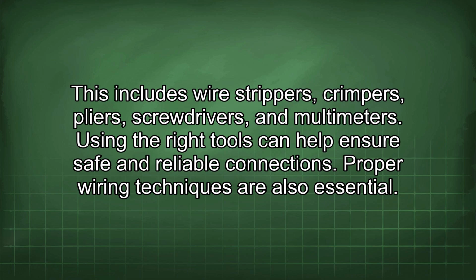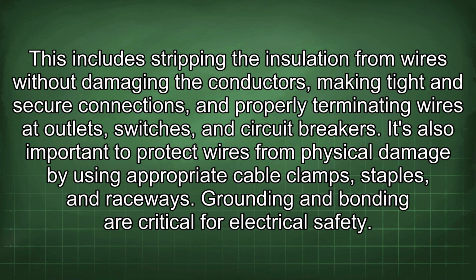Proper wiring techniques are also essential. This includes stripping the insulation from wires without damaging the conductors, making tight and secure connections, and properly terminating wires at outlets, switches, and circuit breakers. It's also important to protect wires from physical damage by using appropriate cable clamps, staples, and raceways.